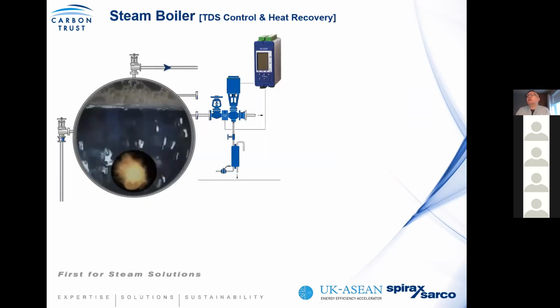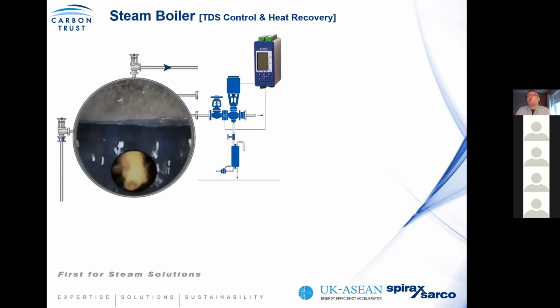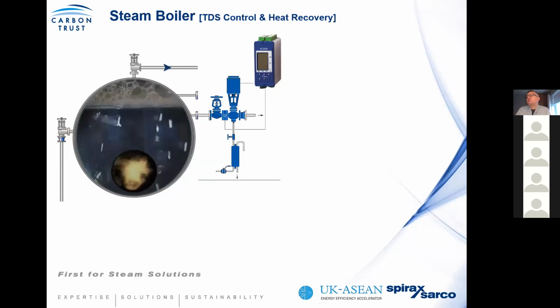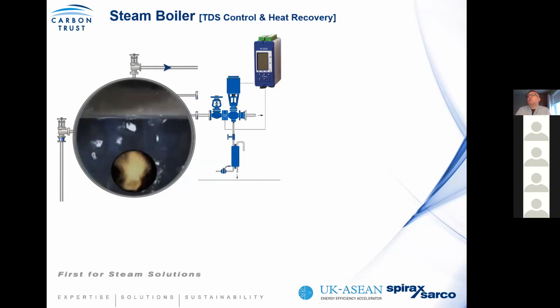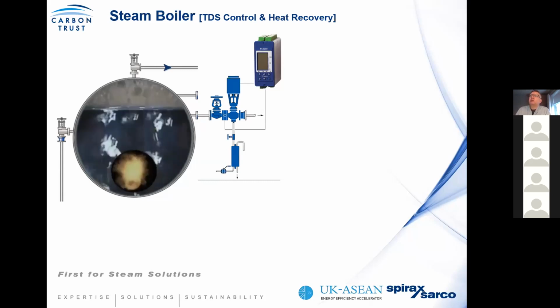When we talk about the conductivity in the boiler, and again, you see the foam layer at the top of the boiler. All boilers have this, and this is purely for demonstration purposes. So unless you're controlling the conductivity in your boiler, there's a greater likelihood this foam is going to be very erratic, and due to the turbulence in the water, you'll find that you end up dragging water into the steam system, which is again an insulator. So it's important that you have continuous TDS blowdown control.